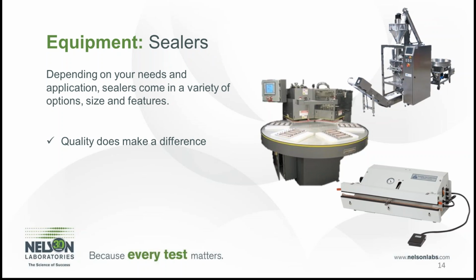Keep in mind that once you have purchased a sealer, the sealer still needs to be validated, hence the IQ, OQ, and PQ. In some instances, portions of these validations may have already been completed. However, it's important to note that even though portions have been completed, it still needs to be captured and documented as part of your validation that these portions are complete and refer to these subsequent documents for those.